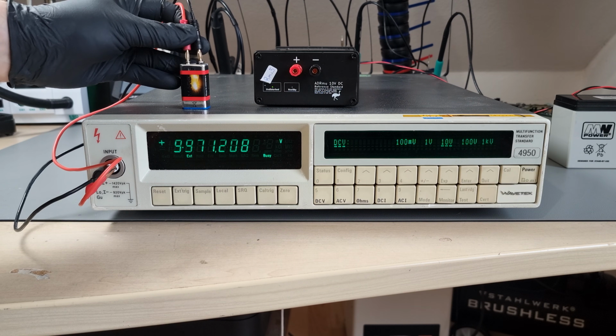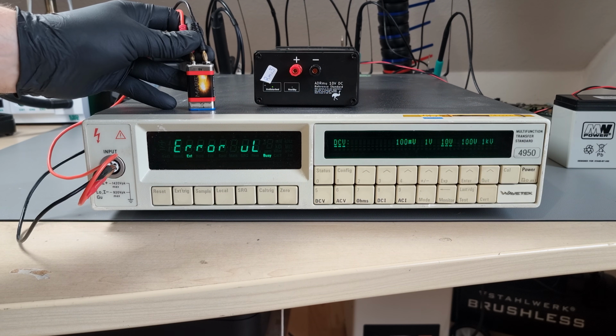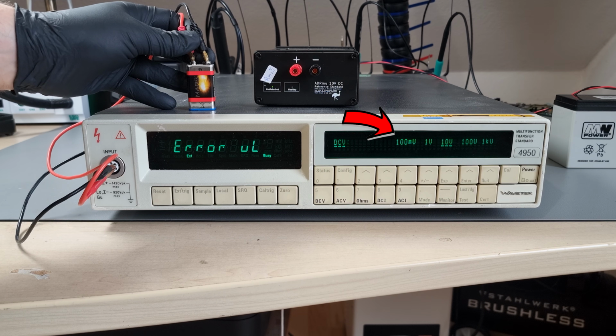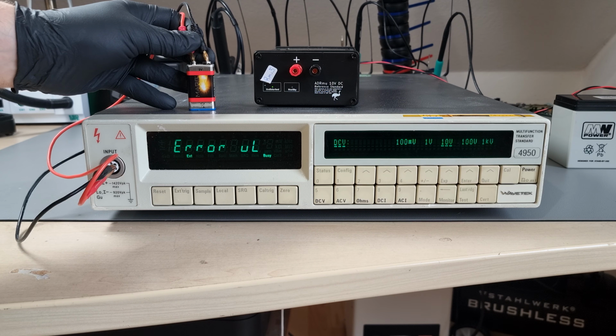Out of every range. This transfer standard will not measure 3, 5 or 7.1 volt. Only its predefined points of interest. It's a bit of a snob in that regard. A likable one though, because this limitation buys us more and tighter tolerance specifications for those measurements that are available.